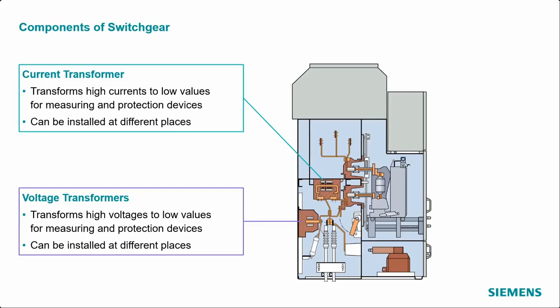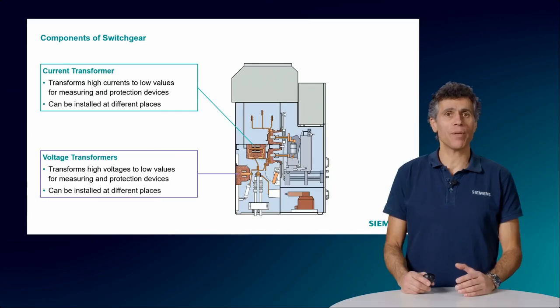Therefore, there are two types of transformers, voltage and current transformers. We could also call them sensors, because their function is to send a signal to the low voltage compartment depending on what they detect on the high voltage side. When there is more voltage or current, the signal is higher. When there is less, the signal is smaller. Transformers are usually used for protection or for measurement purposes.